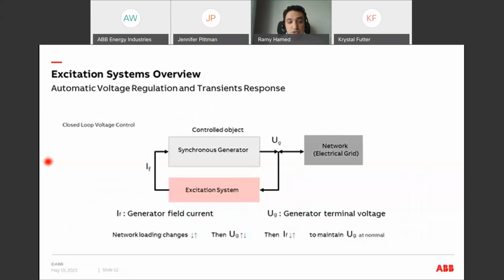Now we move to the second function of the excitation system, which is the automatic voltage regulation, or the closed loop voltage control. The easiest way to understand this is to think of the air conditioning system in your room. If you set the AC in your room to 25 degrees, for example, regardless of the changes in the temperature outside your room, the AC is working to maintain the room temperature at 25 degrees. But for the AC to do this, it needs to always measure the room temperature. And if the room temperature is too high or too low, then it will work to bring it back to 25. The excitation system is doing a similar function.